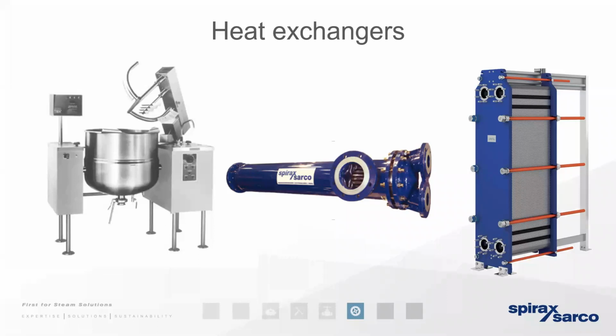They could be shell and tube heat exchangers, or they could be plate heat exchangers. And what you'll remember from that previous presentation is that because condensate as a liquid has far, far less heat energy contained within it compared to steam, we need to get that liquid condensate away quickly. If we don't, that condensate is likely to back up and flood that heat transfer surface area that we need to be full of steam to have a high energy content to keep the process satisfied.